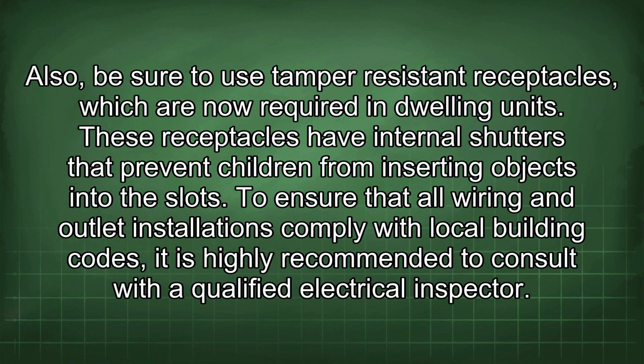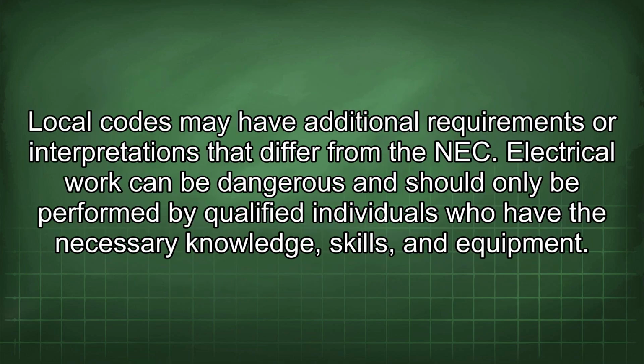Also, be sure to use tamper-resistant receptacles, which are now required in dwelling units. These receptacles have internal shutters that prevent children from inserting objects into the slots. To ensure that all wiring and outlet installations comply with local building codes, it is highly recommended to consult with a qualified electrical inspector. Local codes may have additional requirements or interpretations that differ from the NEC.